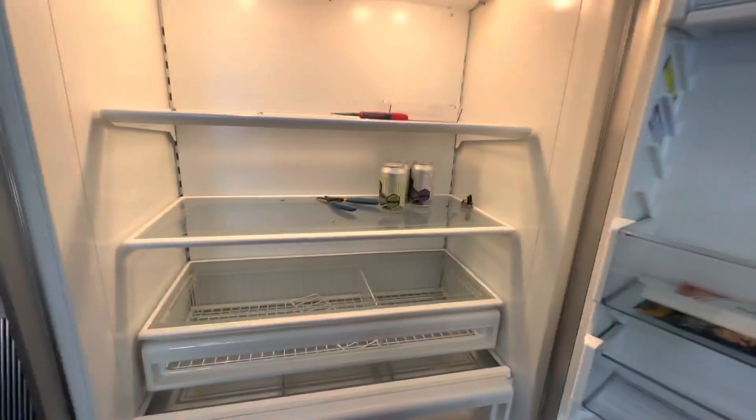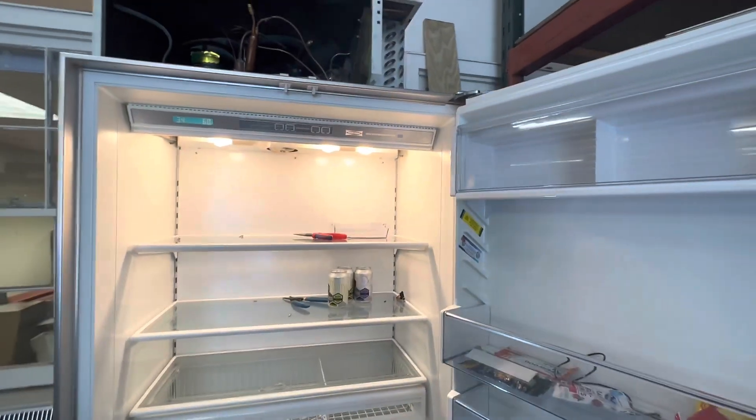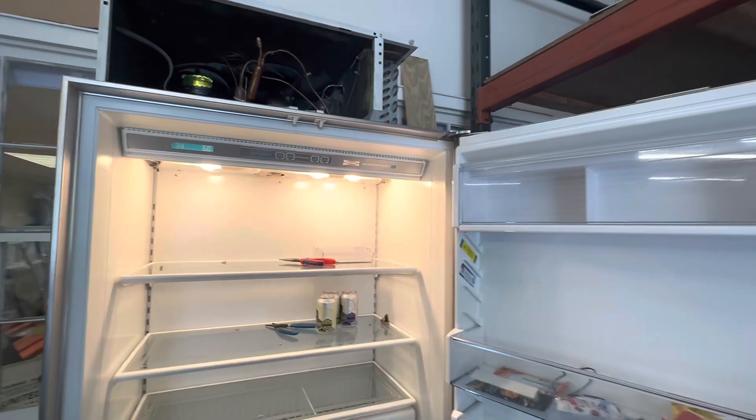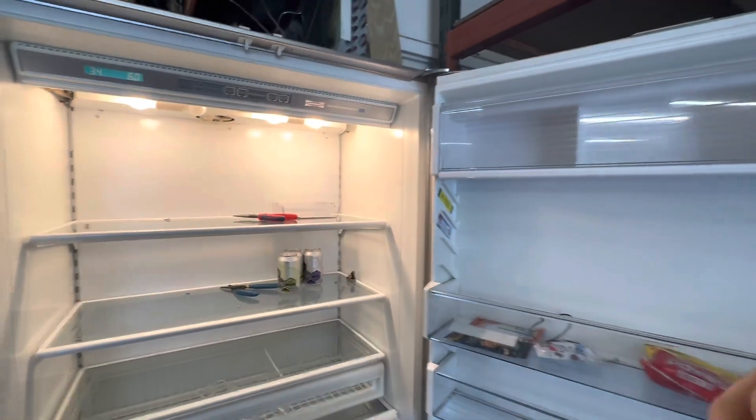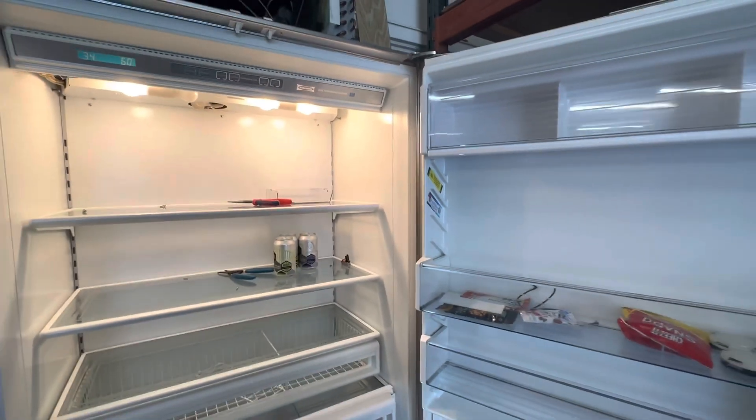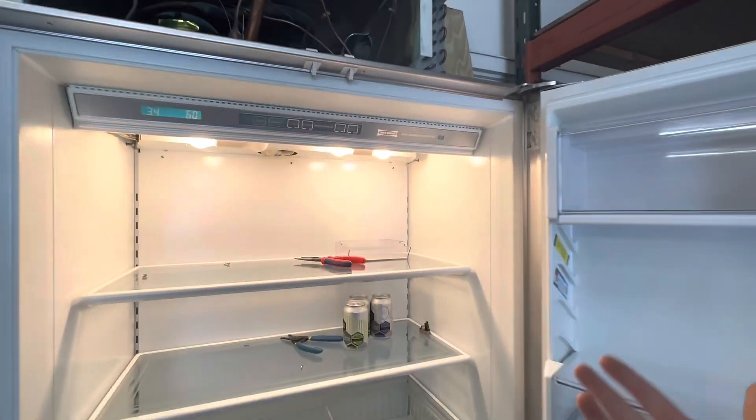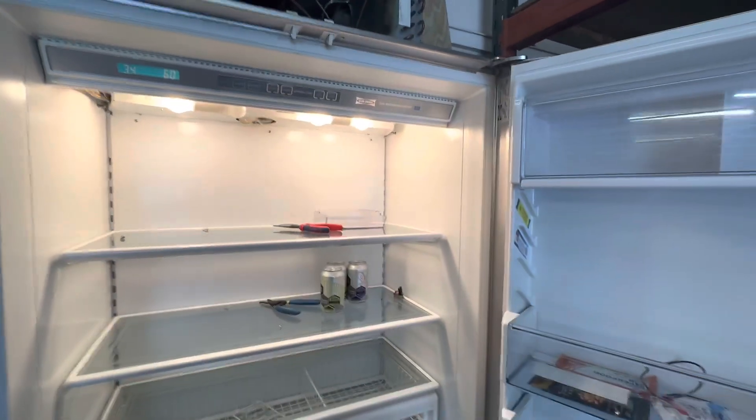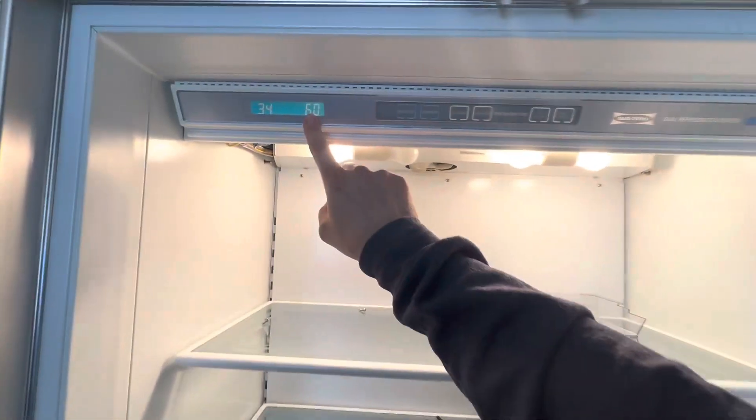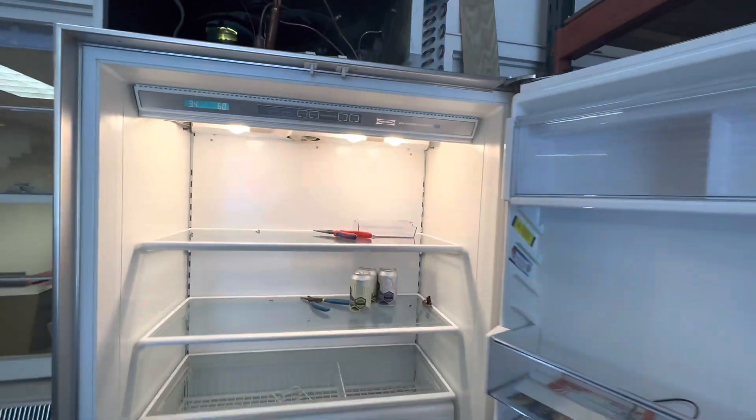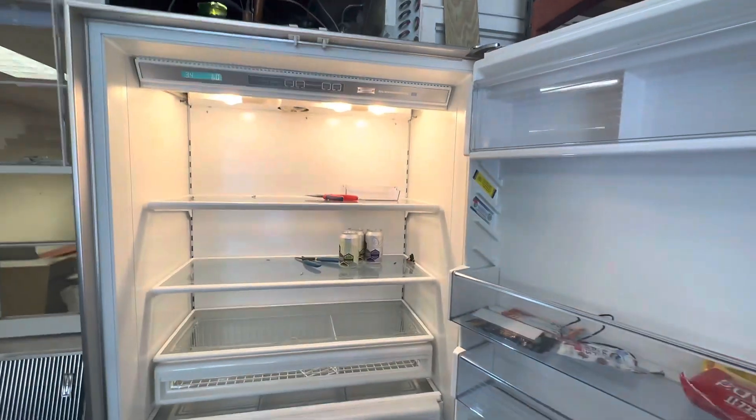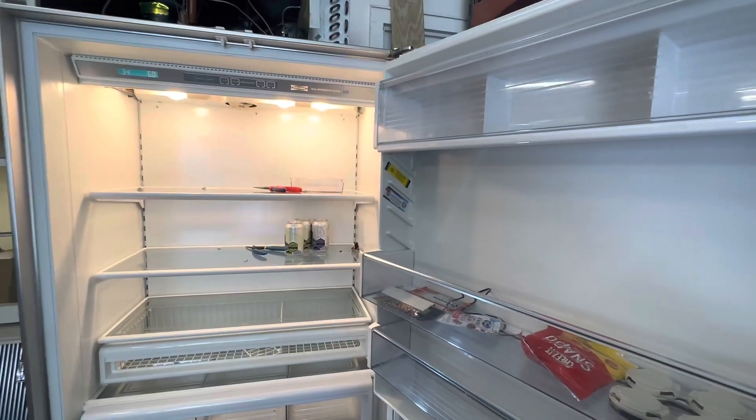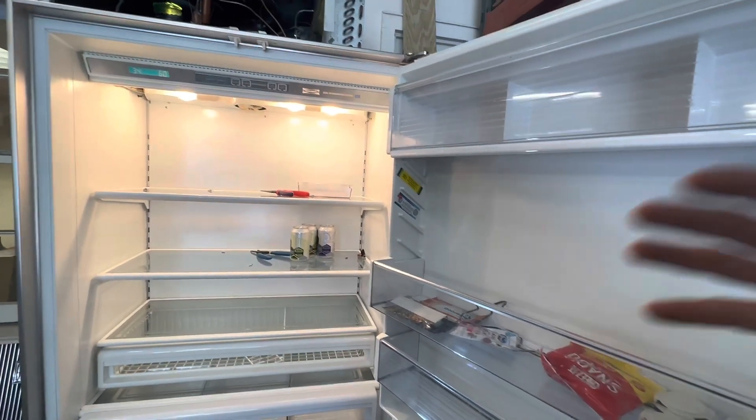The last thing I'll say is let's say that everything's been checking out. We defrost the unit. We turn it back on. We get it cold. We manually put the heaters on. The terminator switch stays closed and it stays closed for a sufficient amount of time for that heater to fully defrost. At that point and probably only at that point would I then focus my attention to the control board. Maybe the control board is not going into defrost and I have a bad control board and my terminator and my heater is just fine.